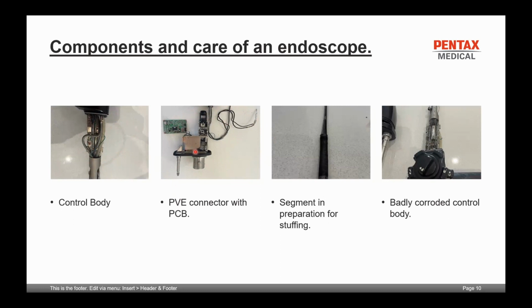This is an image of a PVE connector. On your PVE connector, you'll have everything that is basically coming through from your insertion tube coming out to the connector of the endoscope. You've got ferrite cores to reduce the noise on the imaging. And you have all the Teflon tubings that need to be connected, and that is your PC board that gets connected onto your signal wires. So your remote signal wires and your CCD signal wires will all be connected to a PC board, which is then connected via your electrical connector, which then sends the image and the signals through to your processing unit.